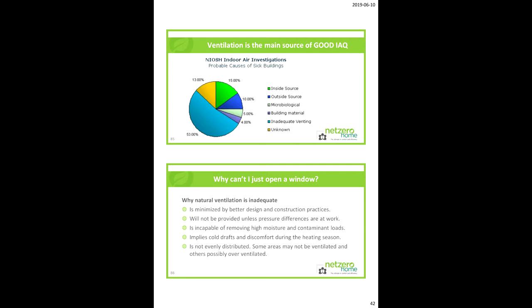You can actually get into issues with humidity control if you rely on implied cold draft. Some people don't like to feel the air, and it's not evenly distributed. Remember, one of the tenets of ASHRAE 55, one of the tenets of 62.2, the tenets of good IAQ, is not just getting fresh air into the home, but where does it need to go — to the rooms where the breathers are. And which room do we do most of our breathing in? Respirations — bedrooms. So that's called ventilation effectiveness, not efficiency. Effectiveness is getting the fresh air to the rooms you need it.